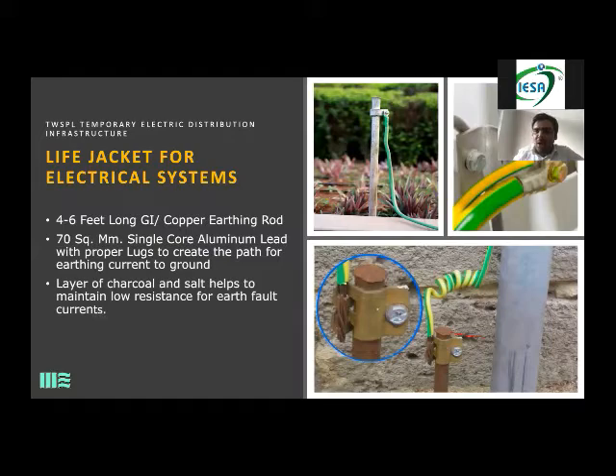If the gensets are parked far away, will it affect the total power output? No. That is a very common question which I've been receiving: is there any power loss? No, there is no power loss. There is a power loss, but everything comes down to undersized wiring. If your genset is parked maybe 300 meters away, I did this last month with a drum. My gensets were parked 300 meters away and we had laid wires of 300 meters for each sound, light and LED.